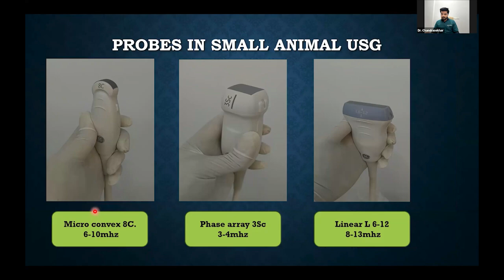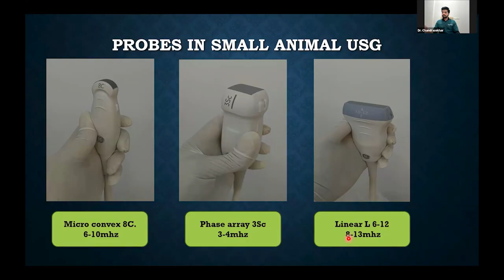So the first probe is your microconvex probe, which emits a frequency from 6 to 10 megahertz. The phased array probe emits a frequency between 3 to 4 megahertz. And the linear probe, which I use for superficial tissue scan, can give a frequency of 8 to 13 megahertz. So let's dive into the actual body of the webinar.